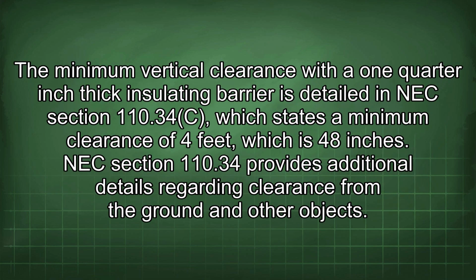The minimum vertical clearance with a 1/4 inch thick insulating barrier is detailed in NEC section 110.34C, which states a minimum clearance of 4 feet, which is 48 inches. NEC section 110.34 provides additional details regarding clearance from the ground and other objects.